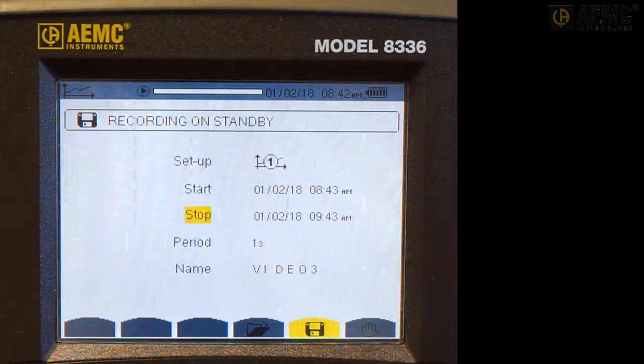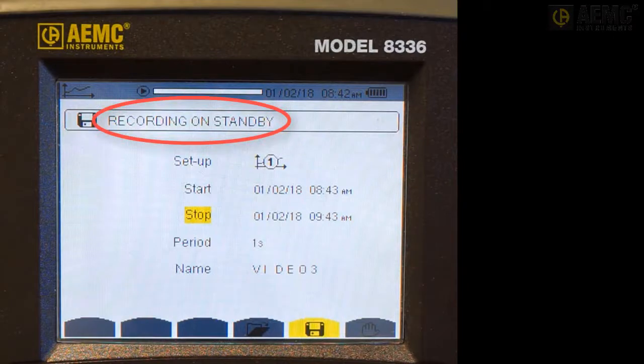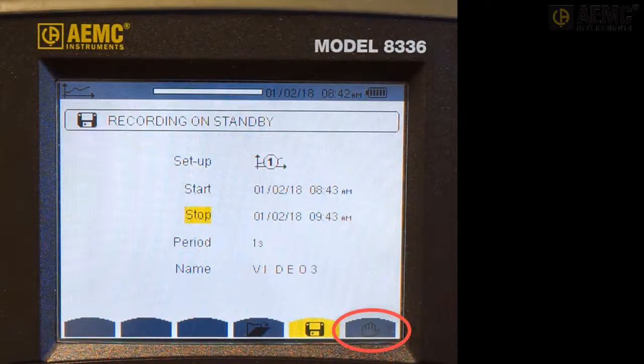Before a scheduled recording starts, the message Recording on Standby should appear at the top of the screen. This indicates all scheduled parameters have been accepted by the instrument and that there is sufficient memory for the recording. While the instrument is in Standby, the right-most Function button changes to a Hand icon. This enables you to stop an active or pending recording. In addition, the Play icon at the top of the screen blinks, indicating that the instrument is ready to record. This icon blinks throughout the active recording session.